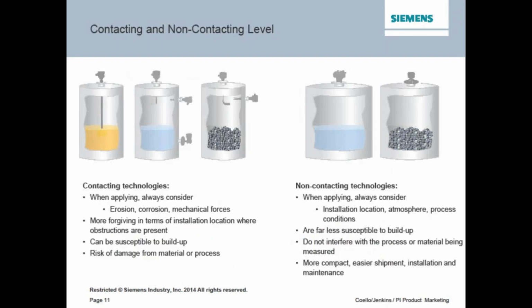There are two different types of level technologies: contacting and non-contacting, which are basically self-explanatory. A contacting technology has some sort of probe or device that extends into the vessel and comes in contact with what's actually inside it. This device might be a guided wave radar or a capacitance probe, and that probe runs the full length of your vessel -- as product rises up the probe, it changes your output, which changes your level reading.